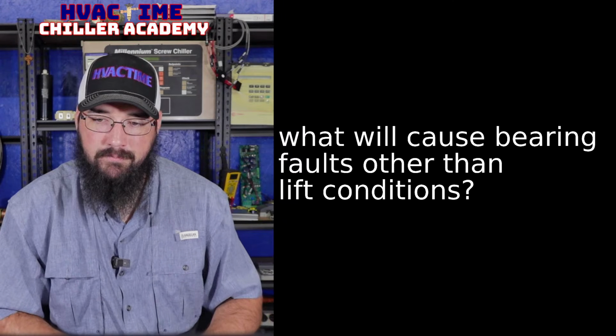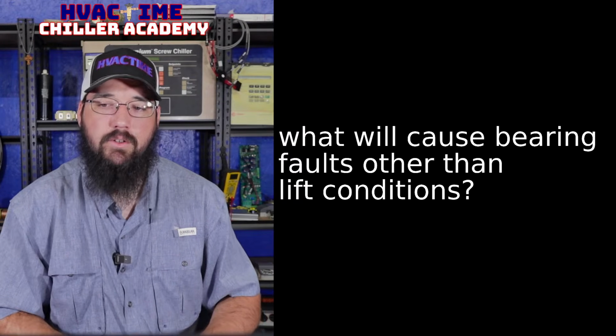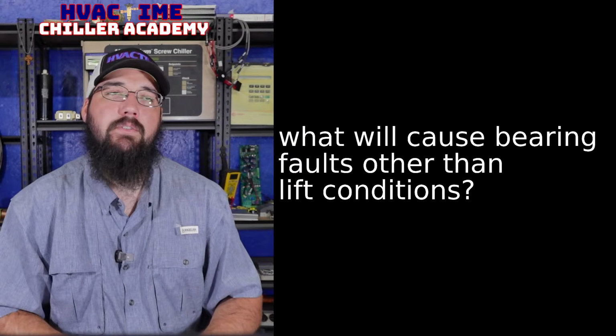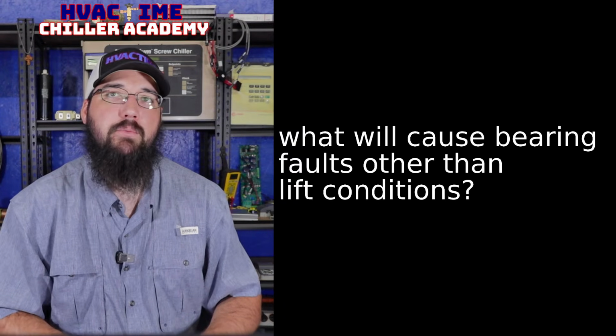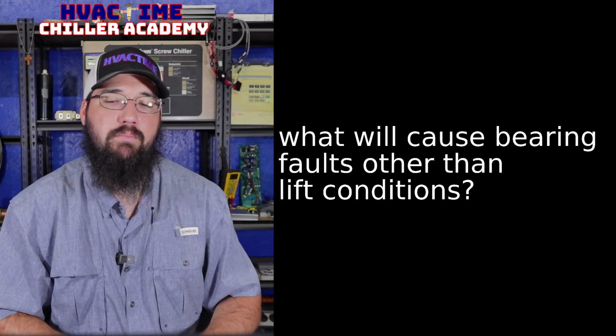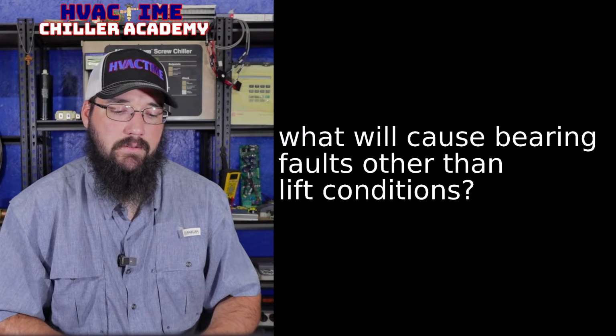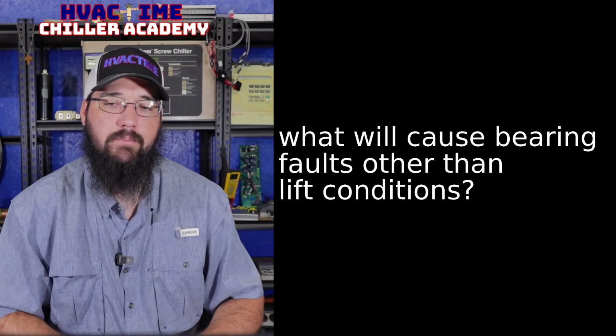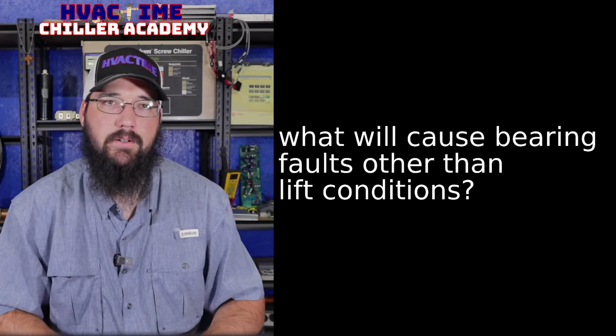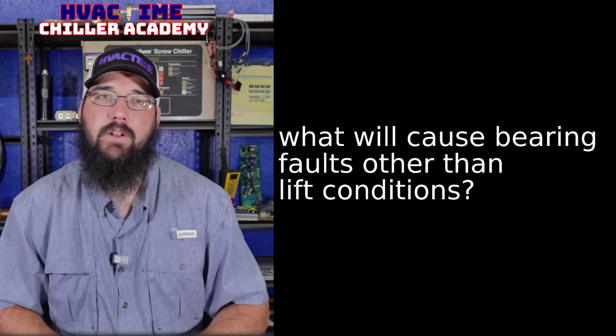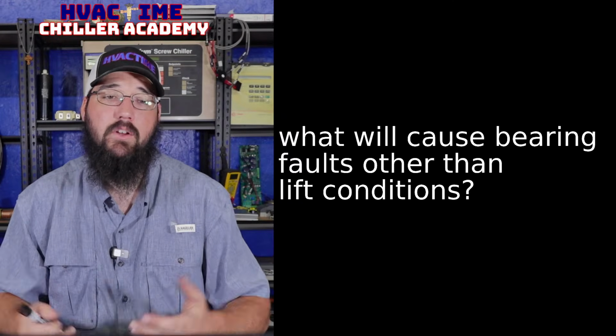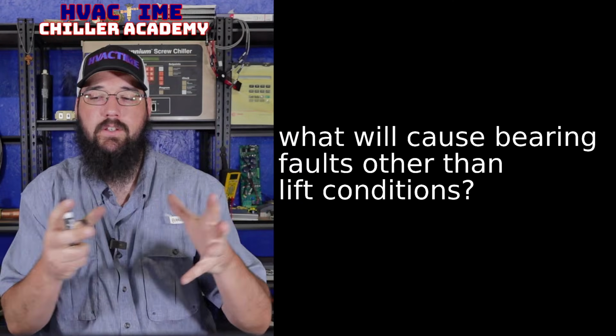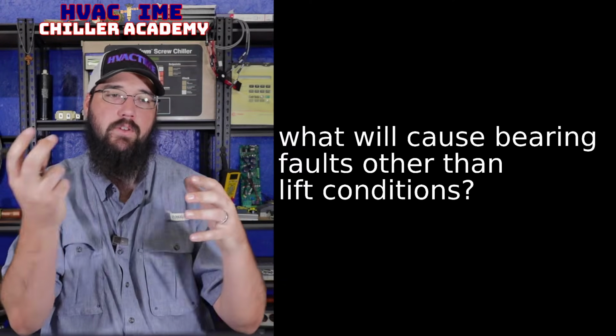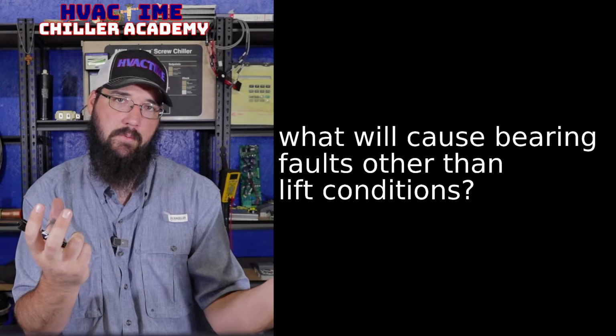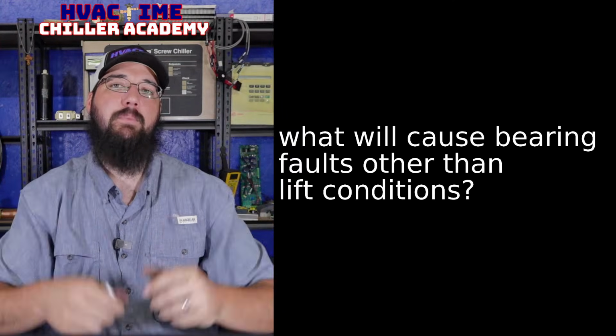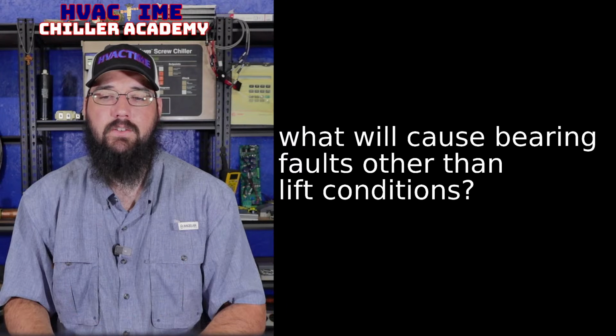Not necessarily. And it could be, even if it's running a high evaporator level, you may not see it reflect the same on both compressors. Now they shouldn't be horribly far apart from each other, but they may be just different enough to where one is seeing it where the other one's not. Because all that plays into where the suction line is in orientation to the evaporator. This one's pulling from this point on the evaporator, this other one's pulling from this other point. How that pulls back up into the suction, all of it gets affected in that process.